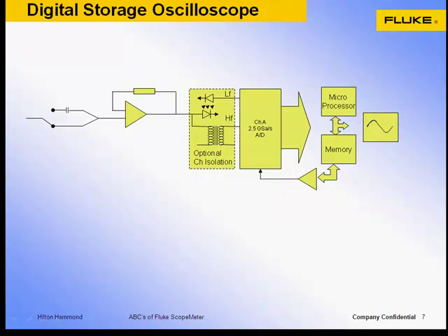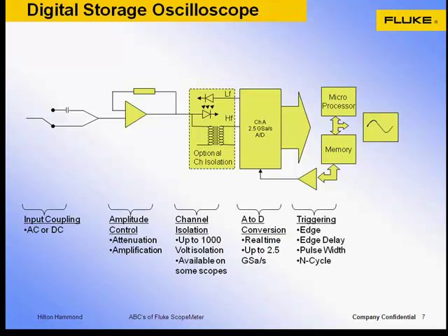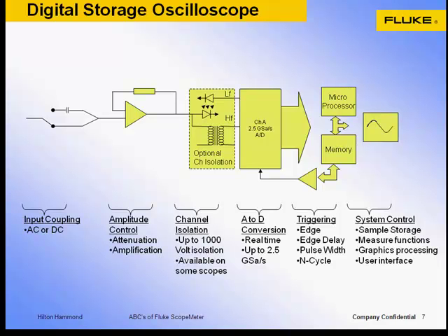Here's a quick overview of a digital oscilloscope's architecture. This will familiarize you with the key functions that control the acquisition and display of a waveform trace. The block diagram shows how the unknown signal is passed through a series of signal conditioning circuits. These circuits control the coupling, attenuation, amplification, gain, such that the unknown signal applied to the ADC converter is within known limits.